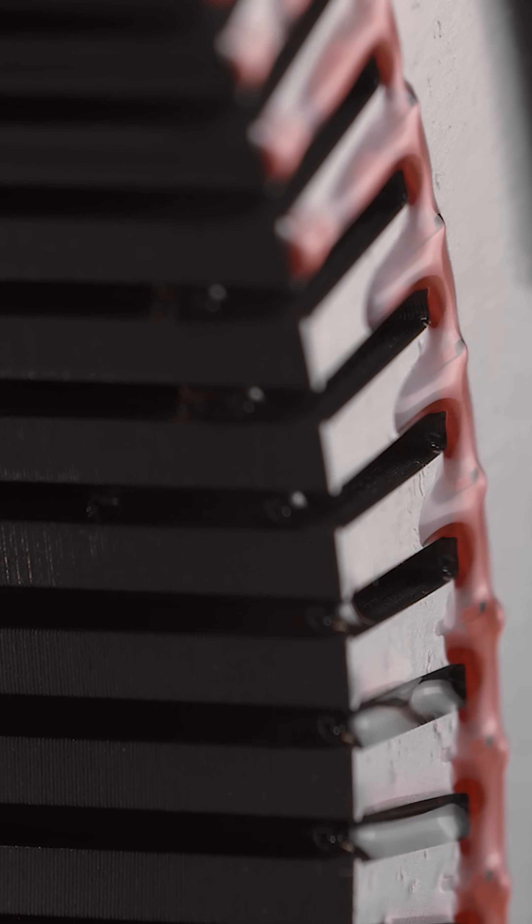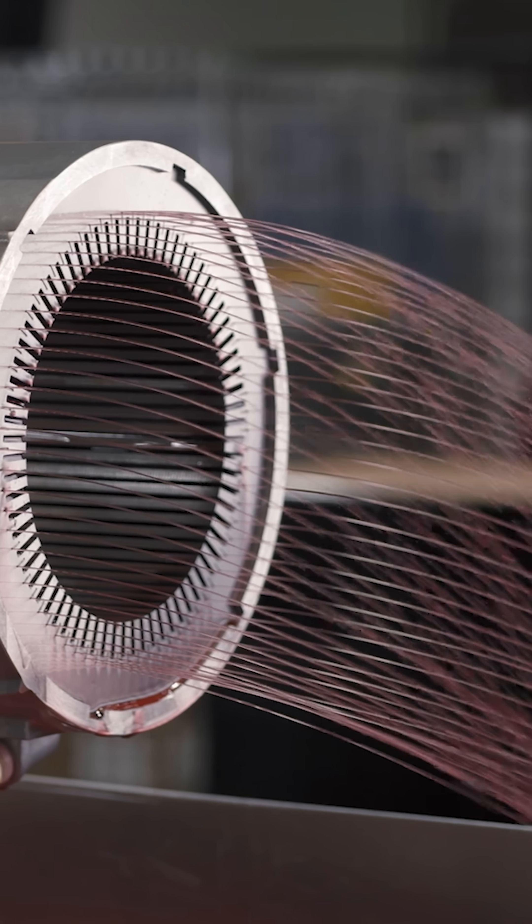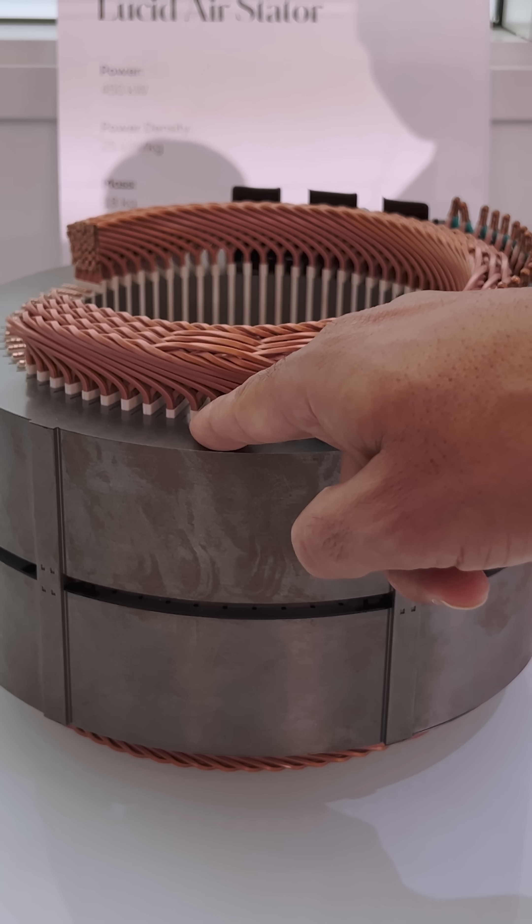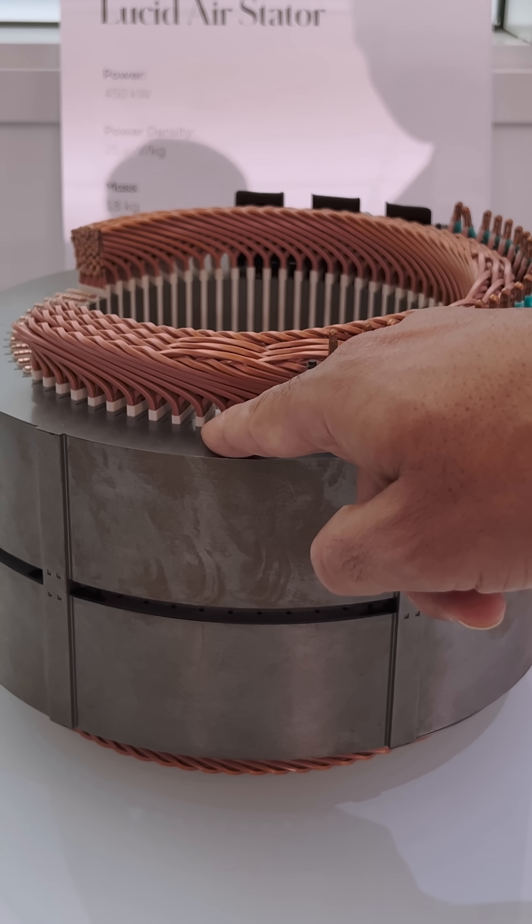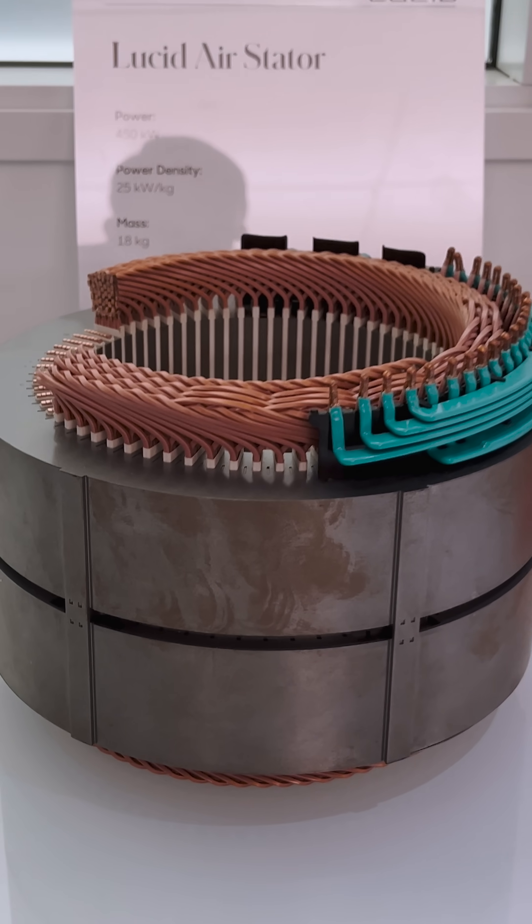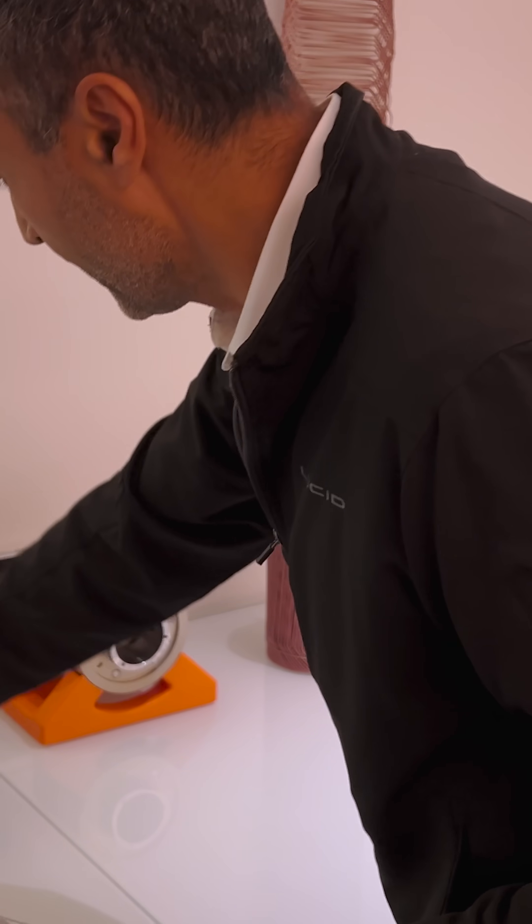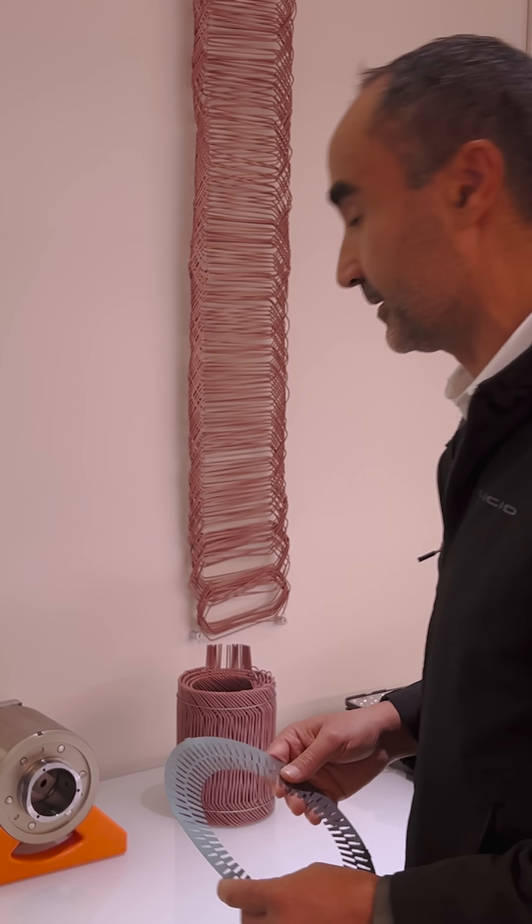We have a video, maybe we can show it and share it with you, that shows these channels, which we call the microchannels in this case, allowing this jetting effect, the fluid with velocity hitting the end winding, creating much more heat transfer out of the same oil fluid dynamic system.